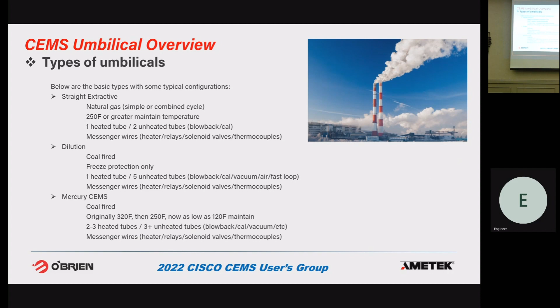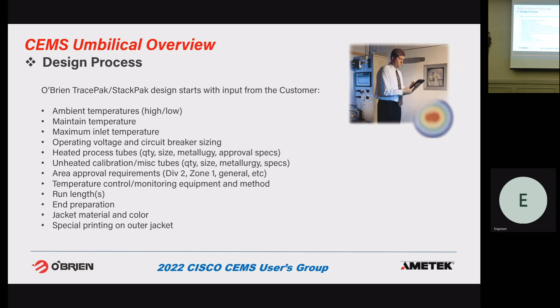So the 3 main styles of probes, everybody knows, it's already kind of been gone over. So for us to properly design a heated tubing bundle, these are some of the things that we need from the customer. Ambient temperatures, maintained temperatures, maximum inlet temperatures. These are all the things we need to be able to figure out what tubes, what electric tracing we need to use, circuit lengths, breaker sizes, if you have a hotter than normal inlet coming in. We also have, I'll go over later, different end preparation options, jacket materials and colors, and we do offer special printing on the outside of the bundle.